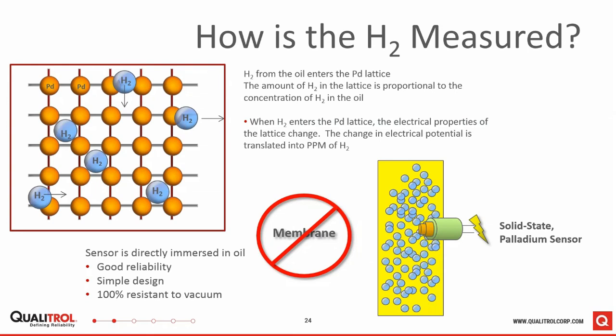Since it's a solid-state device, it's immersed in the oil or indeed left in the headspace. And since the sensor does not degrade as part of this measurement process, the sensor makes the measurement without being consumed by the measurement, which is a common feature of sensor technologies. This type of sensor doesn't degrade over time, so it's really well suited to difficult to reach applications where you want to install it and forget about it.